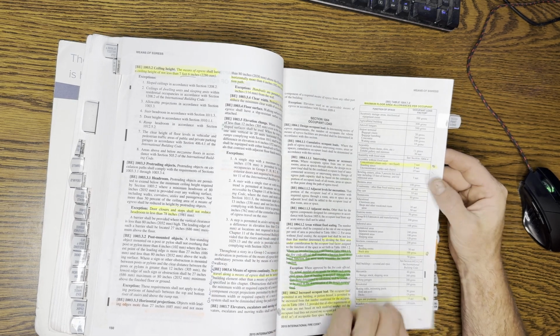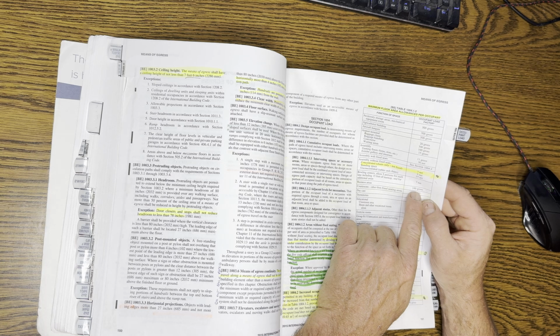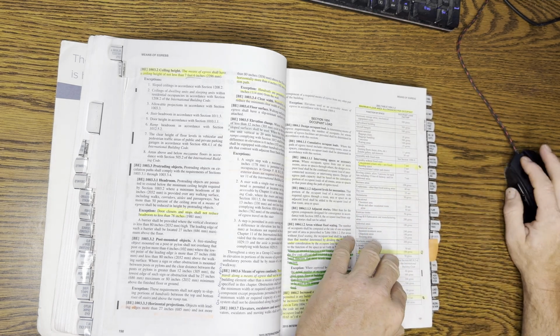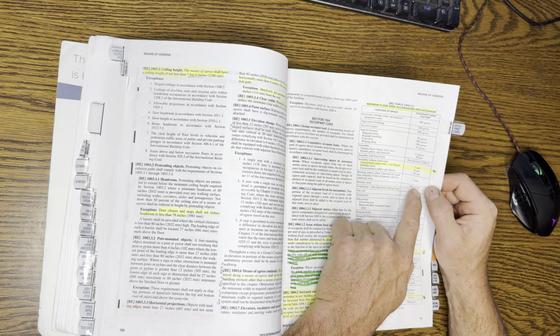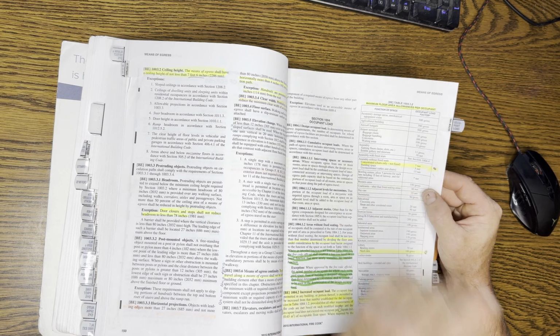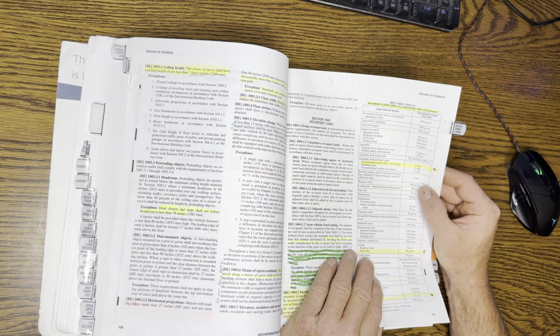Okay, let's just jump. Oh, yeah, one other thing, I want to point out something just to show how flexible this is. The General Services Administration, the GSA of the United States of America, did a survey in 2009 and found that their particular estimates for government buildings were 150 square feet per person, not 100 square feet per person. So in 2018 and subsequent versions of the IFC and IBC, both IFC and IBC, it's 150 for this number. So that's just additional evidence. Don't get caught up on this. This is 100. New versions of the IFC say 150.